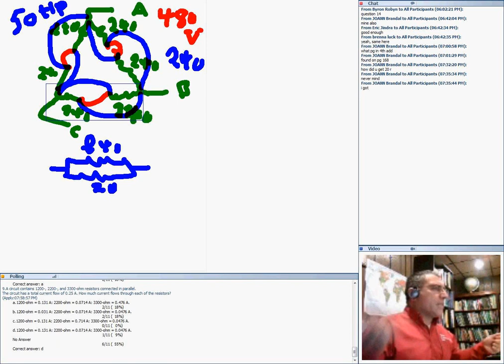I've seen electricians burn equipment because they didn't pay attention to seriesing or paralleling coils to get higher or lower voltage. If you series the coils and put it on 240 instead of 480, remember motors are dumb. If you give them 240 instead of 480, they'll draw more current to compensate for the voltage loss and burn themselves out. You don't want to burn a 50 horsepower motor on expensive equipment.